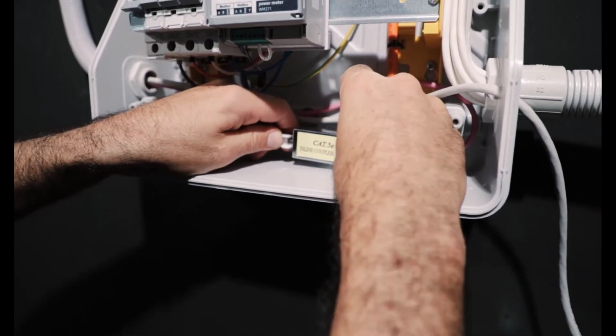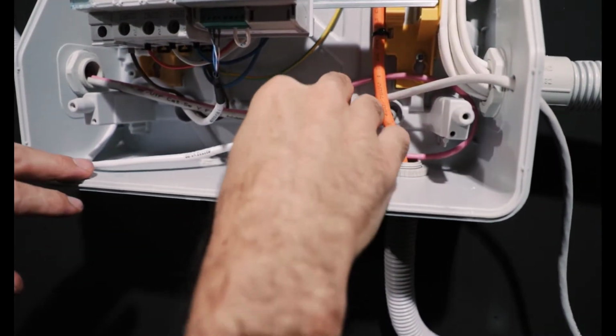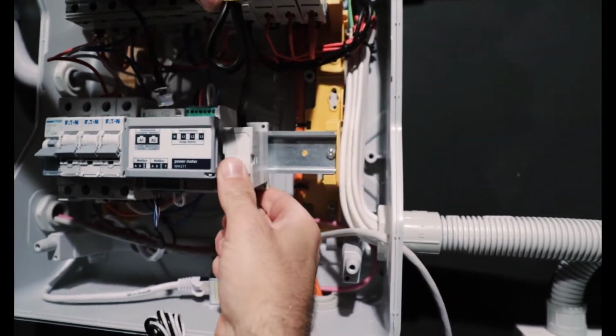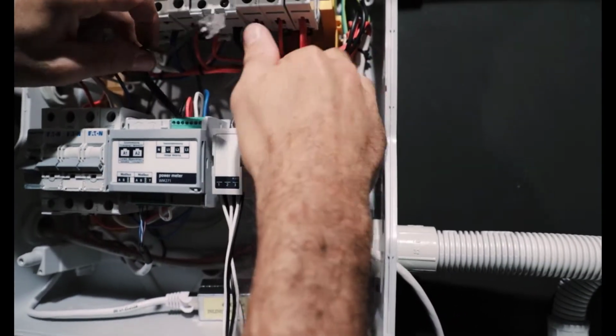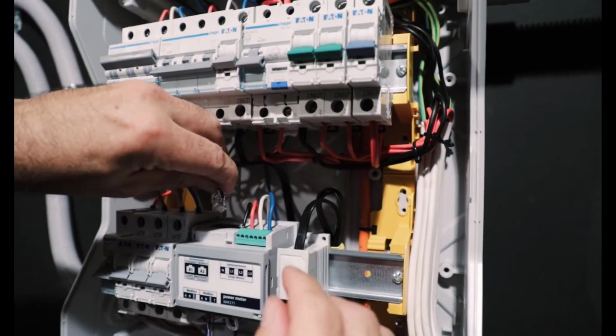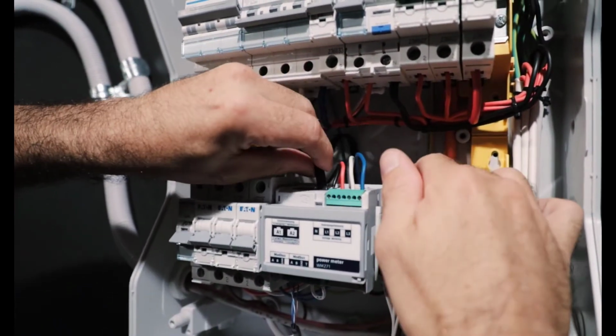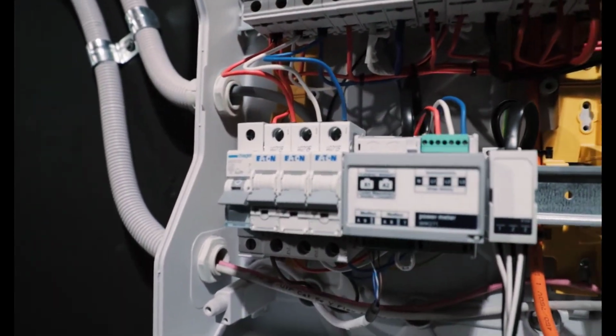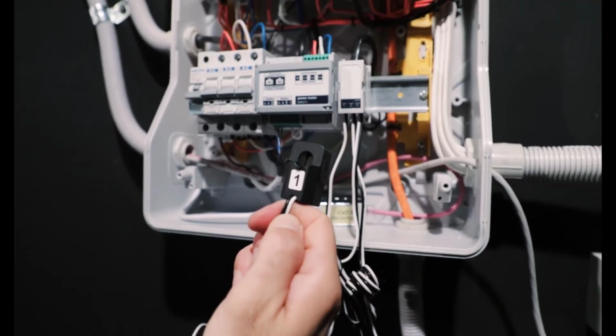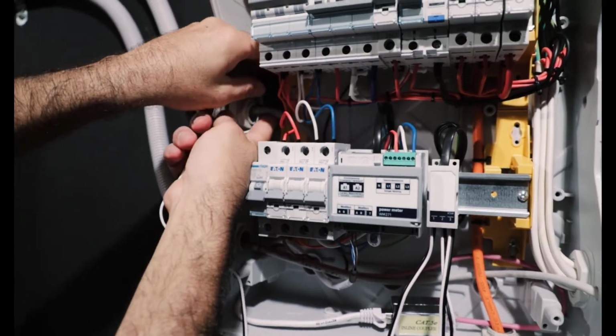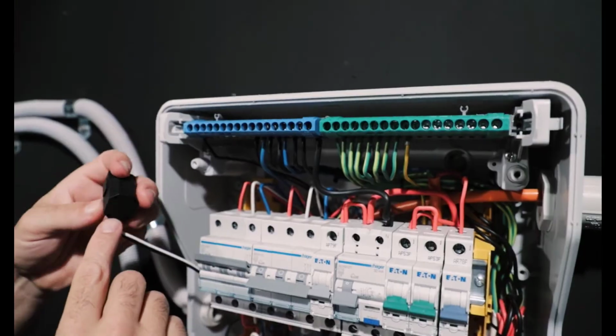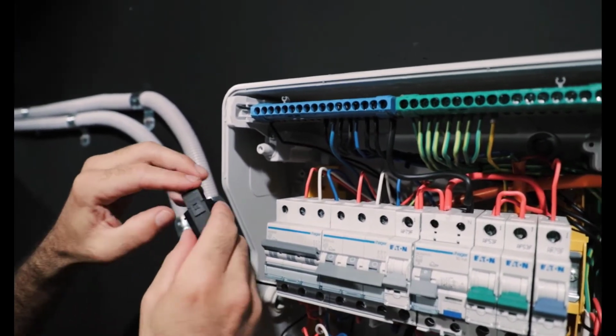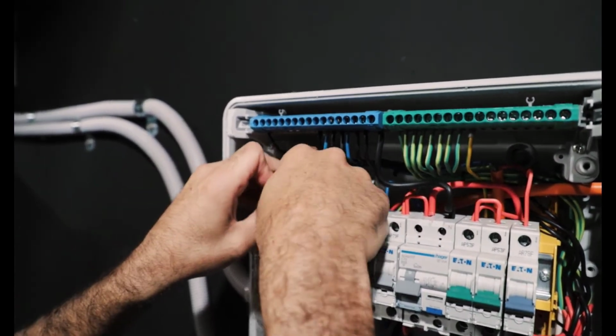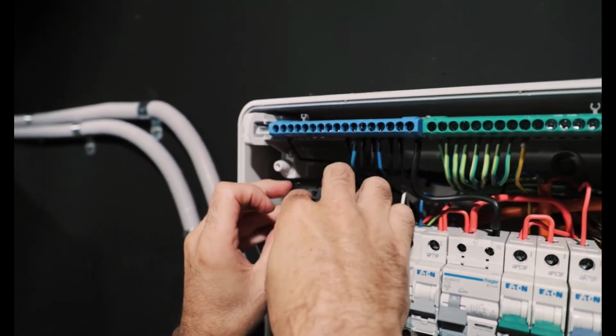As usual, we then connect up the Modbus connection, and there we have it. The meter is in place. All we now need to worry about is getting all of the CTs in place. So CT set number 1 going into A2, we're just going to be looking at consumption. So what we're measuring here is the power in and out of the main grid connection point. So purely grid measurement.